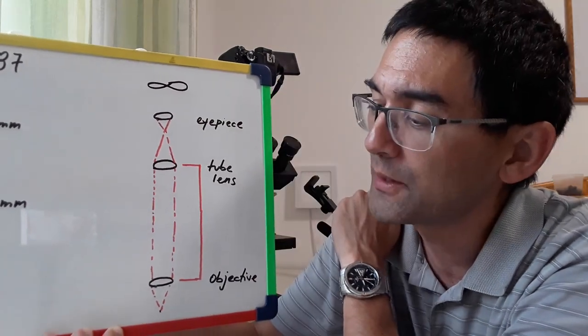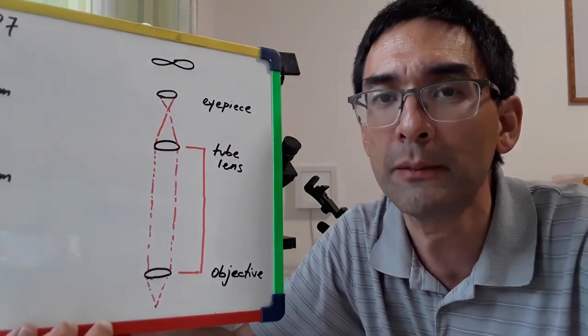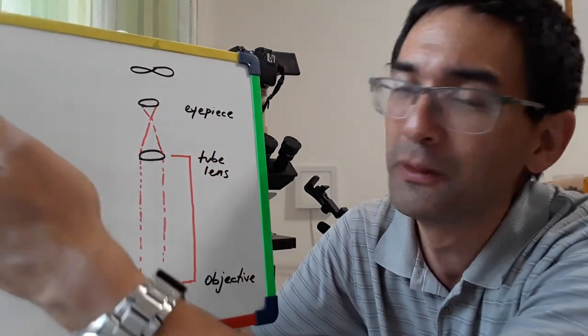And this one is actually now responsible for focusing the light to a point so that it's projected here and then the eyepiece can pick it up just as normally. So the disadvantage now is with those infinity objectives is that they're not compatible between different manufacturers and of course they're also not compatible with microscopes that do not have a tube lens.